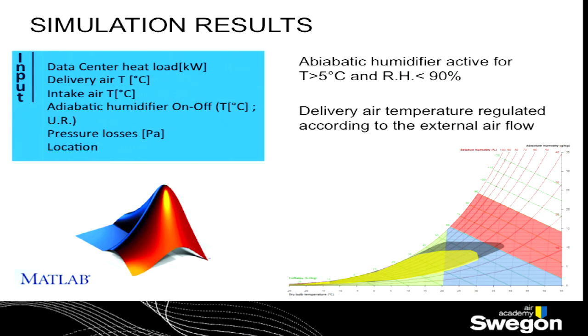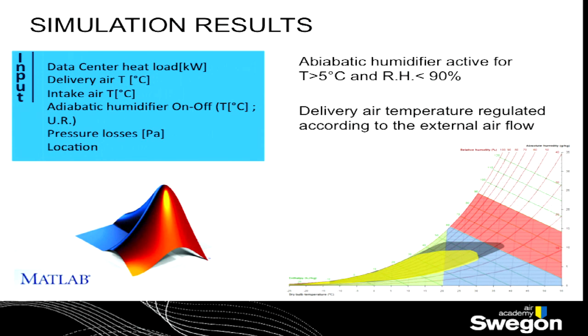We performed our analysis with MATLAB, considering an adiabatic humidifier which is active for temperatures higher than 5 degrees. Why? Not because 5 degrees are not enough to have a total free cooling, but because the energy spent adding the adiabatic cooling is less than what we earn decreasing the speed of the fan. So we have a benefit in switching on the evaporative cooling system at the lowest temperature possible. Of course, not lower than 5 degrees because of a problem with the ice. So these are the conditions for the calculation that we are going on now.